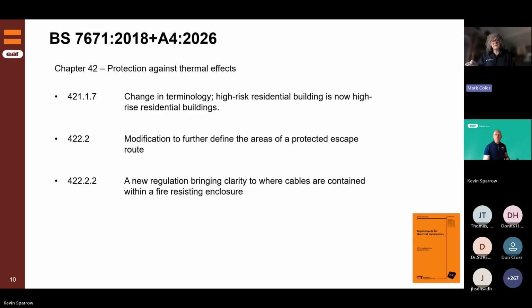The previous requirement was that you shall not run cables through this area - it might be easier to get through that way, but you couldn't take cables, so you'd have to go around, and what a fight that would be. What's changed this time is that you can take cables through that area, but they've got to be boxed in a fire-resisting enclosure to make it as impervious as if it wasn't there. So that's a new change that's gone in.